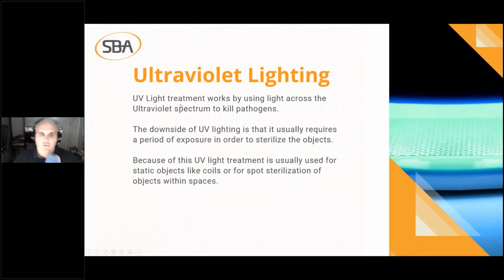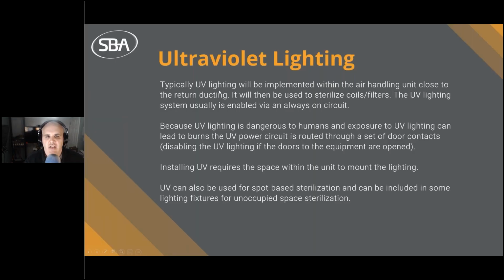Ultraviolet lighting. So UV lighting works by using light across the ultraviolet spectrum to kill pathogens. Now, the downside of this lighting is that it requires a period of exposure in order to sterilize objects. Now, that's fine if you're sterilizing a coil or a filter, or if you're doing spot sterilization of a space. It's not necessarily applicable to sterilizing an airstream. And that's why you'll see a little bit later in this presentation, I say that IAQ technologies are really a combined strategy. So when we look at UV lighting, typically what's going to happen, right?